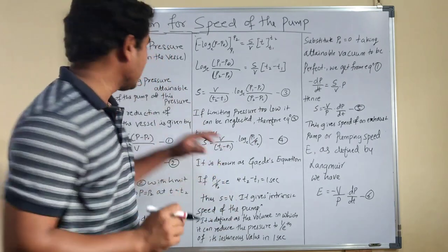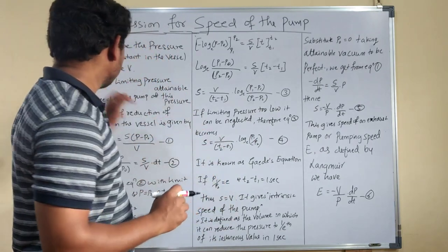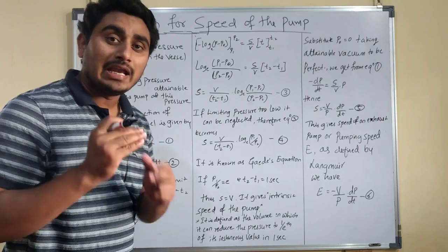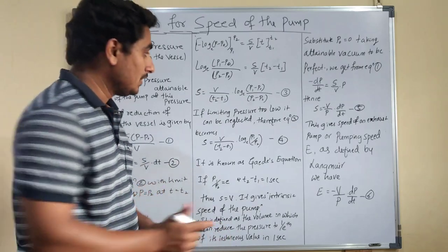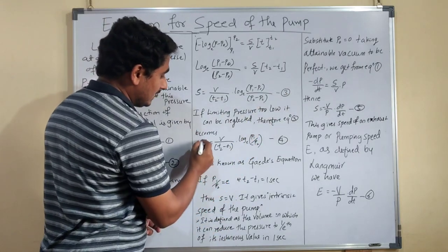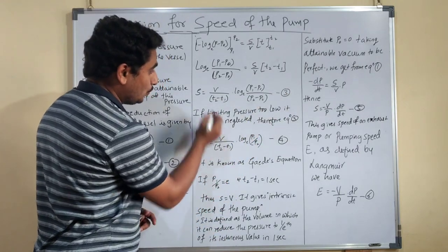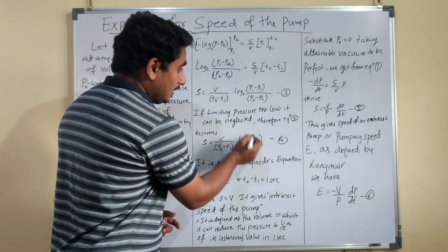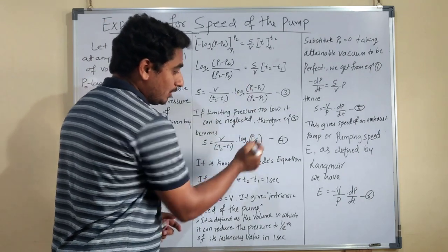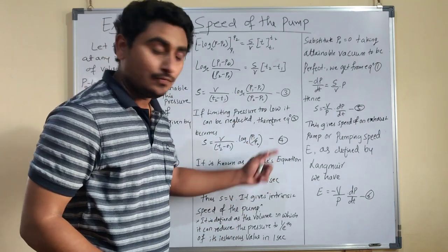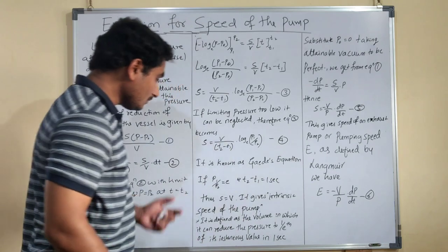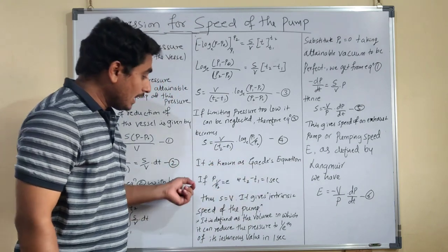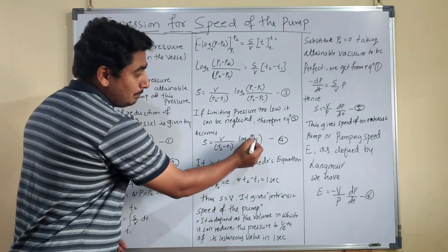If the limiting pressure P0 is very low, we can neglect that term, so equation 3 becomes: S = V/(t2 − t1) · log(P1/P2). This is equation number 4, known as the Gaede equation.